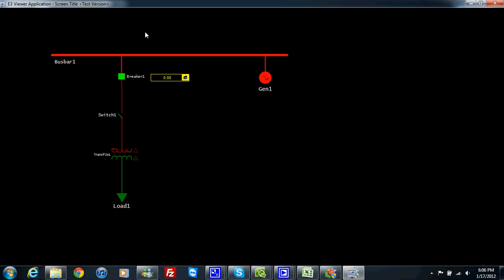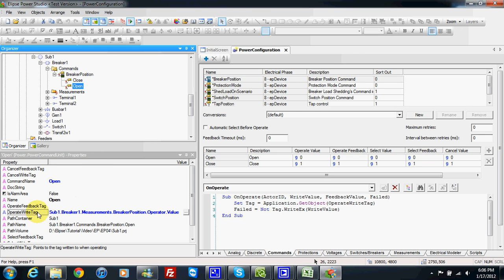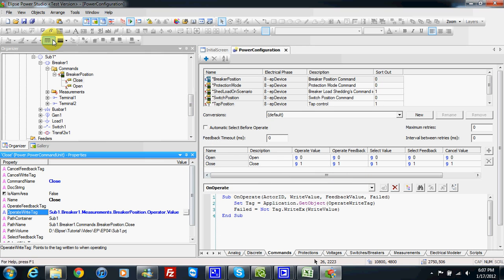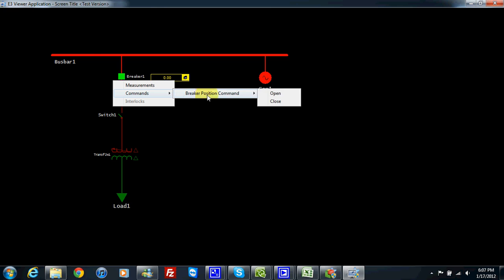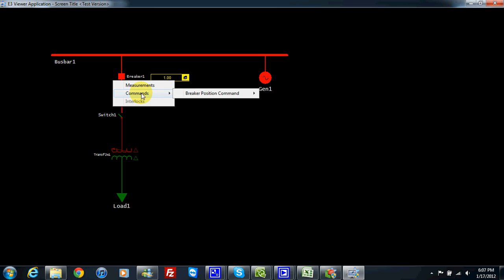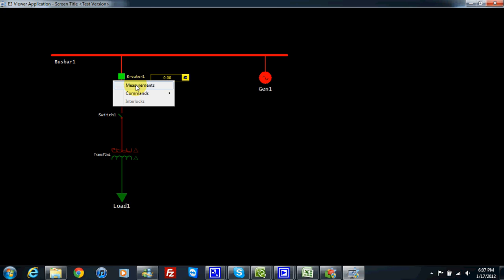Now we have one command. If I click on breaker one, here I have a command which is enabled, and in command I have the breaker position — I can open or I can close. For the open command unit I already know where to write the tag. For close, I also choose to write directly to my breaker position operator value. If I run my project, the breaker is currently open. I choose close and send a command — then the breaker is closed. If I want to open: command, breaker position command open — yes, then it is open.